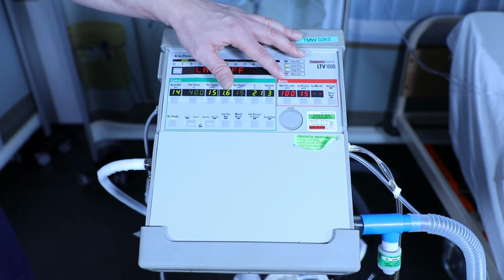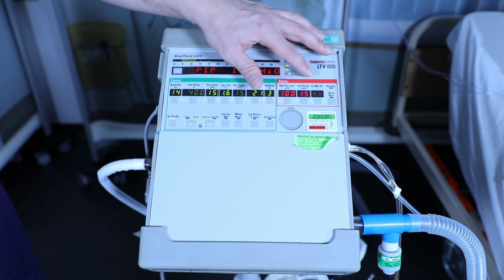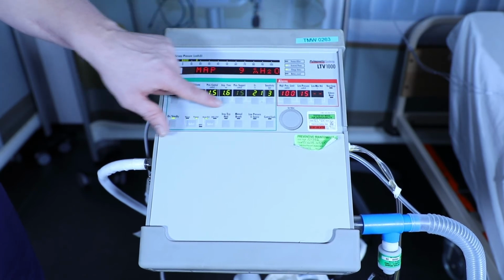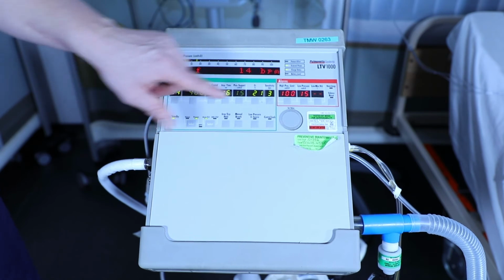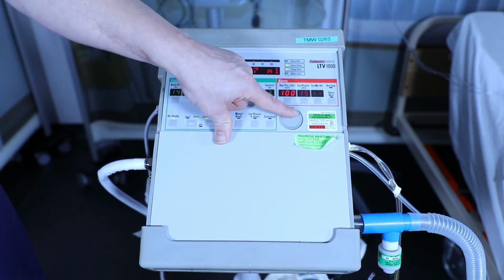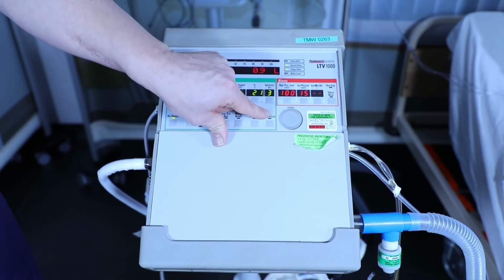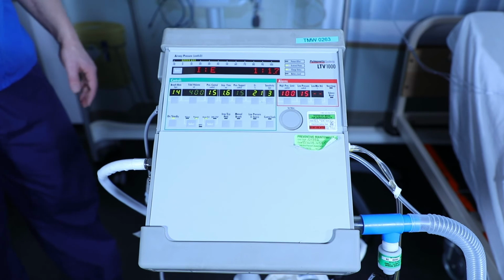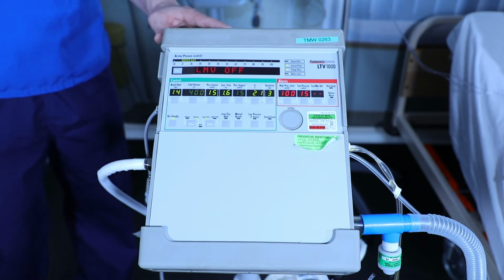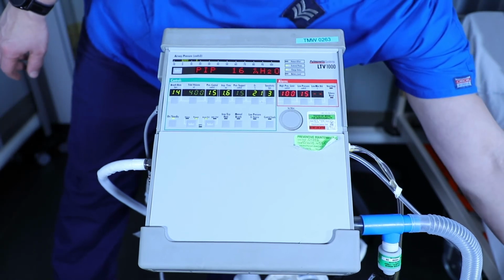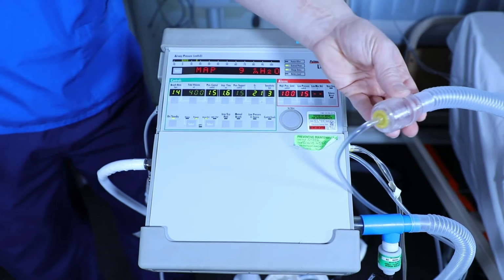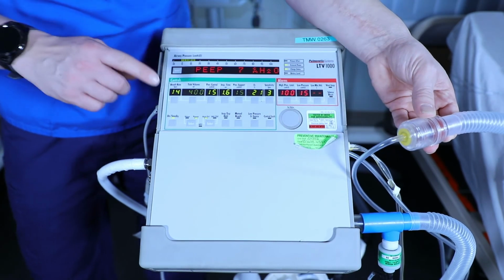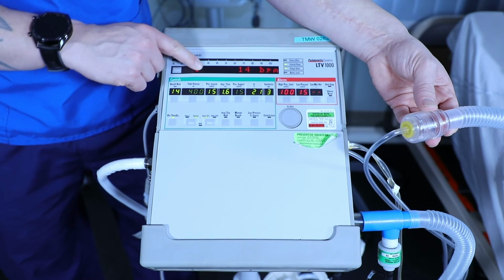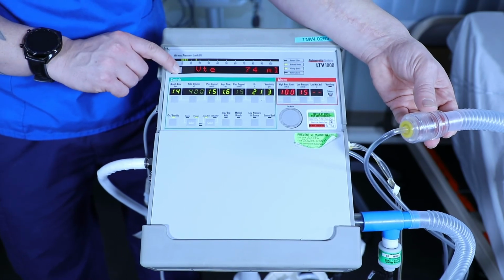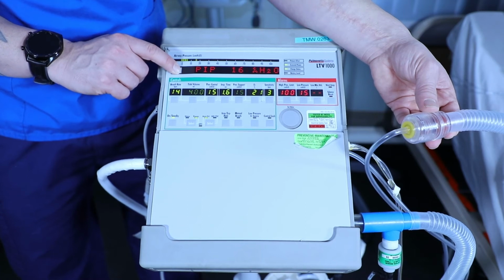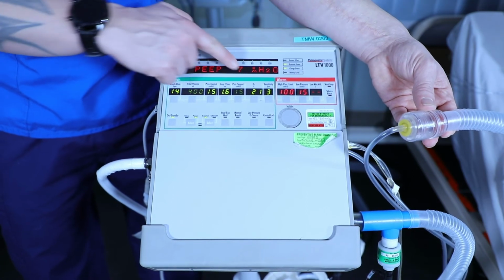Over on the far side we have our external alarms, as we call them: high pressure limit, low pressure limit and low minute volume. These are set in identical ways to the functions over here. Press the limit we wish to set, using the jog dial up and down, and then press to select. Now, one of the slightly more unusual aspects of the LTV is that the PEEP is delivered via an external PEEP valve. So in order to set the PEEP, it must be done here. Now, we're on PEEP at the moment, but as the display scrolls through, we want to be able to see the PEEP that we're delivering. So if we press the select button until PEEP appears, this should keep this on this screen whilst we change.